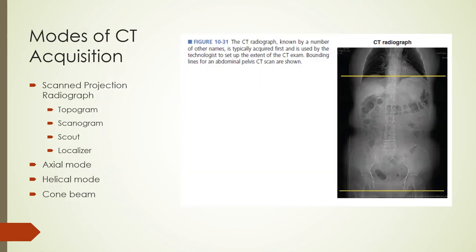The beginning of most CT acquisitions is a scanned radiograph — a radiograph of patient anatomy acquired with a fixed tube and detector orientation, no rotation, and the patient translated through the scanner bore. It is called by different names by different manufacturers. Once the radiograph is obtained, technologists can plan the scan by defining the extent of the scan, kV, mA for manual scans, field of view, pitch, and whether an axial or helical mode will be acquired.